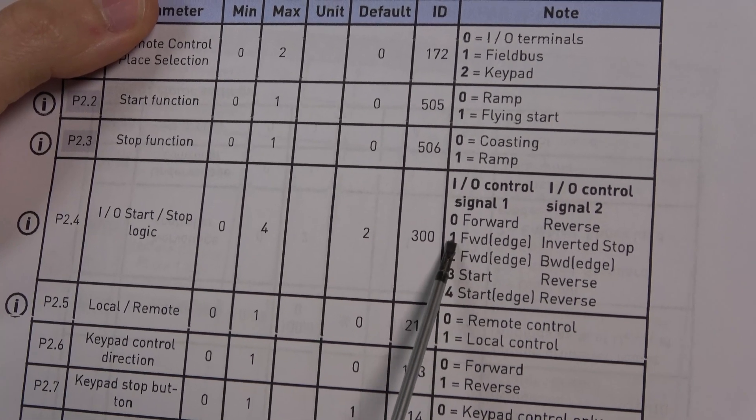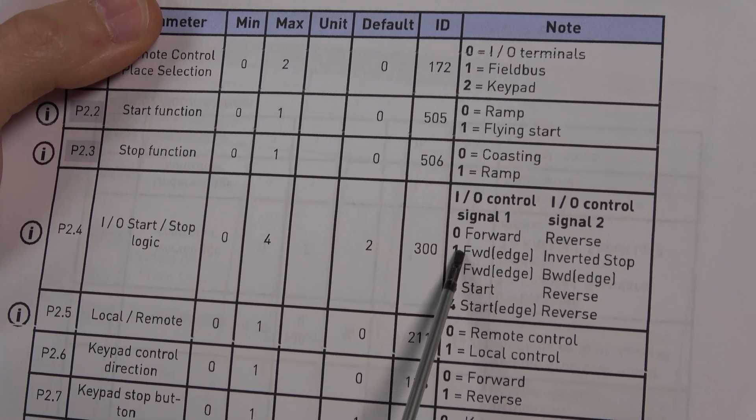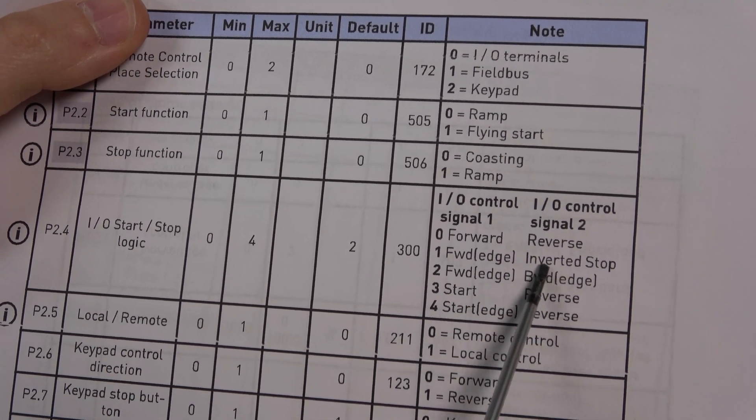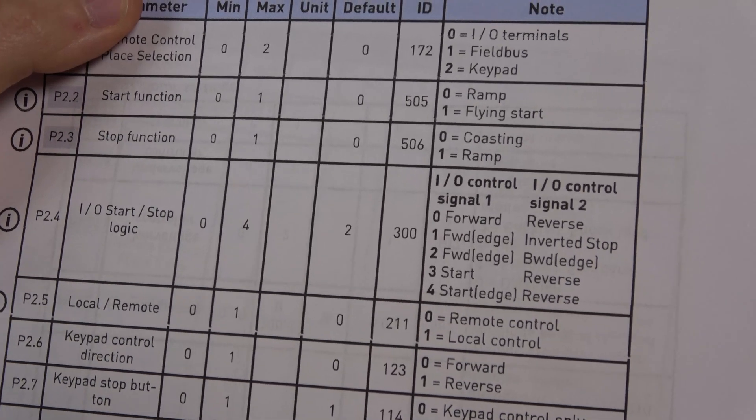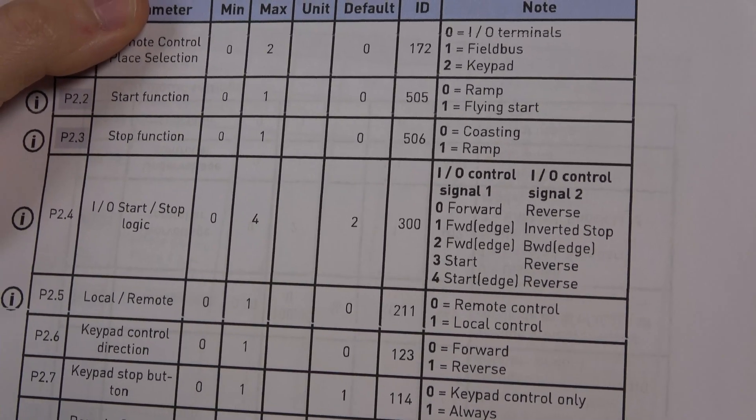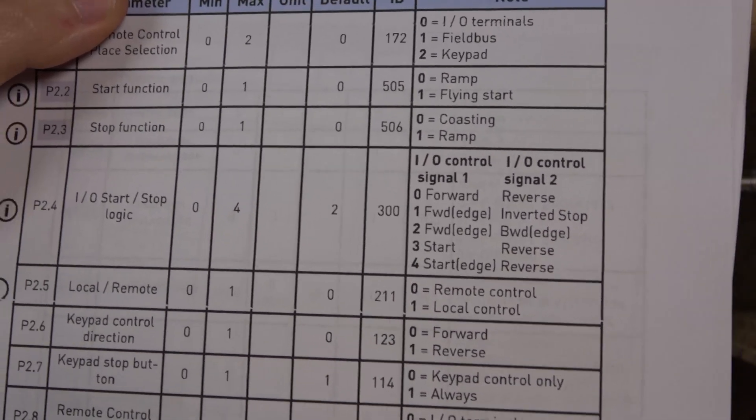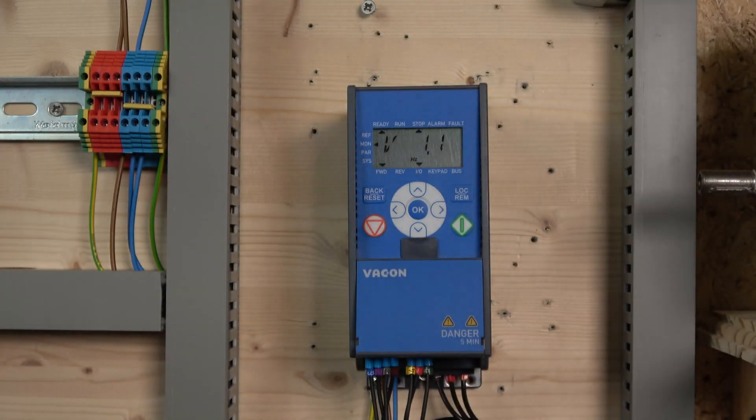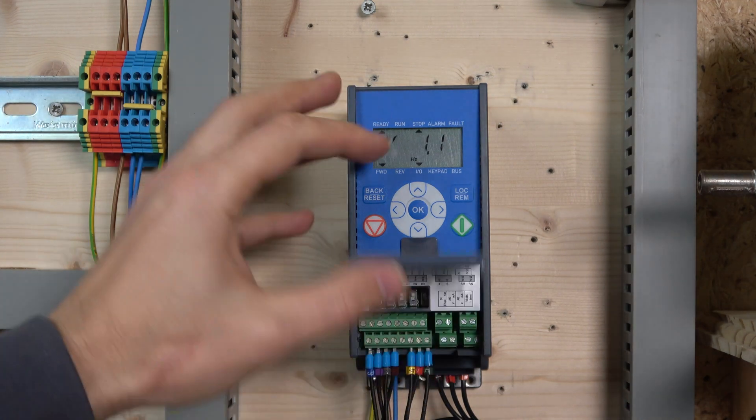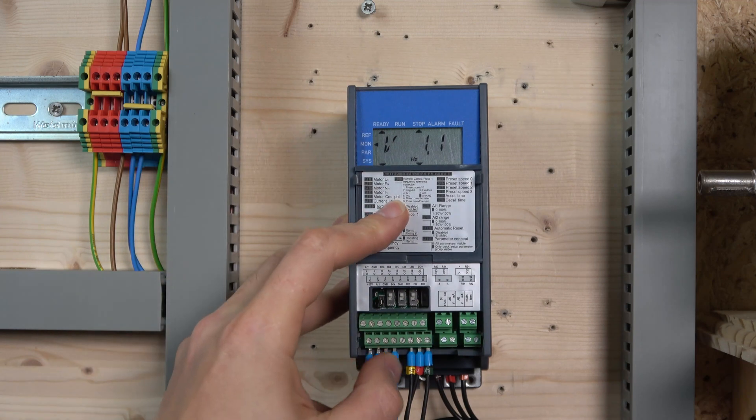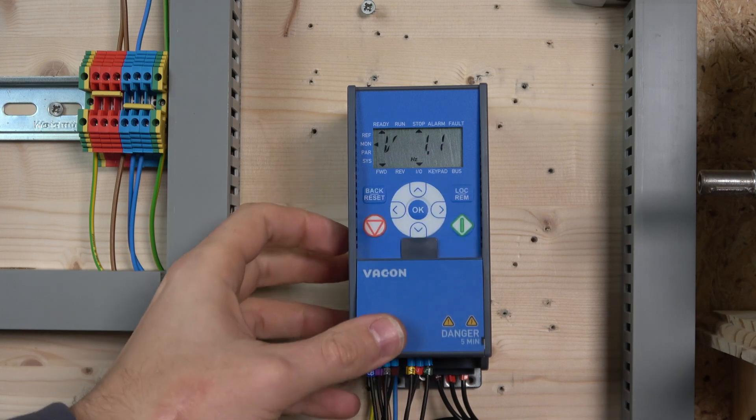The inverted stop will latch the input. It does the same for reverse, which we need to program into digital input 3. Once we change that, we reprogram digital input 1 as start and digital input 2 as stop.